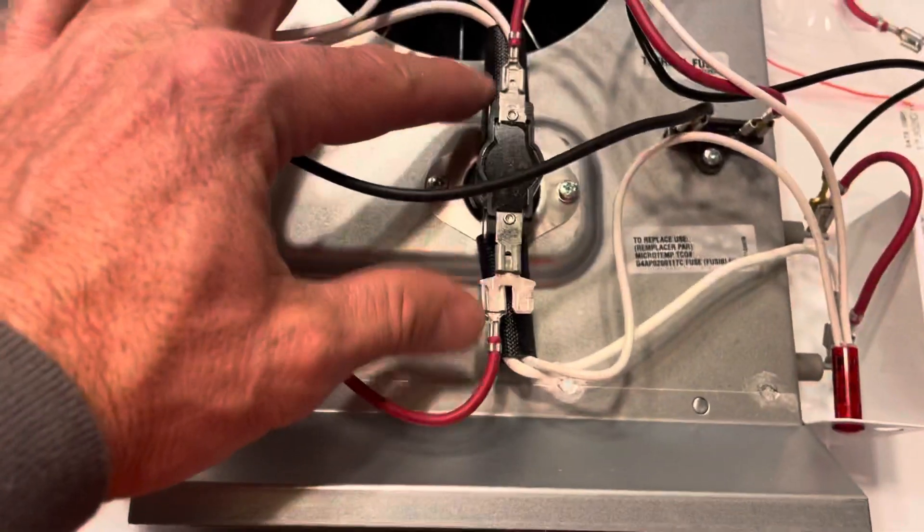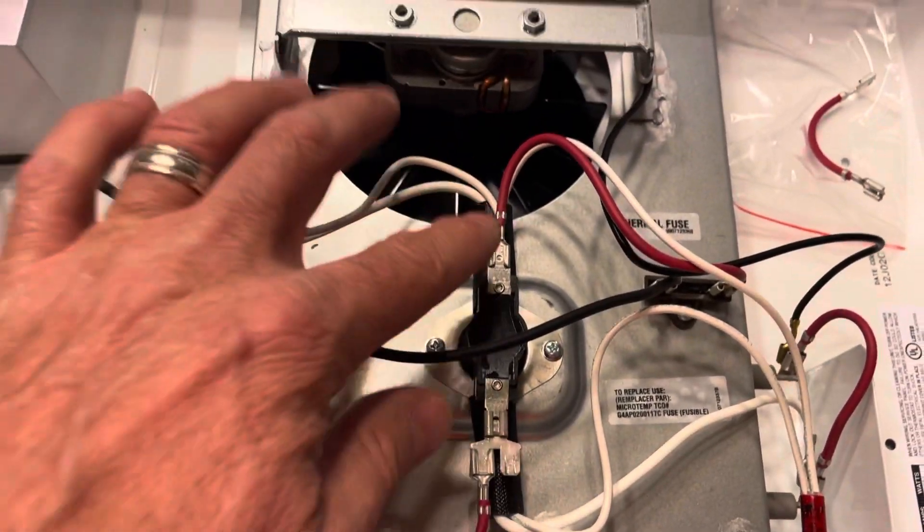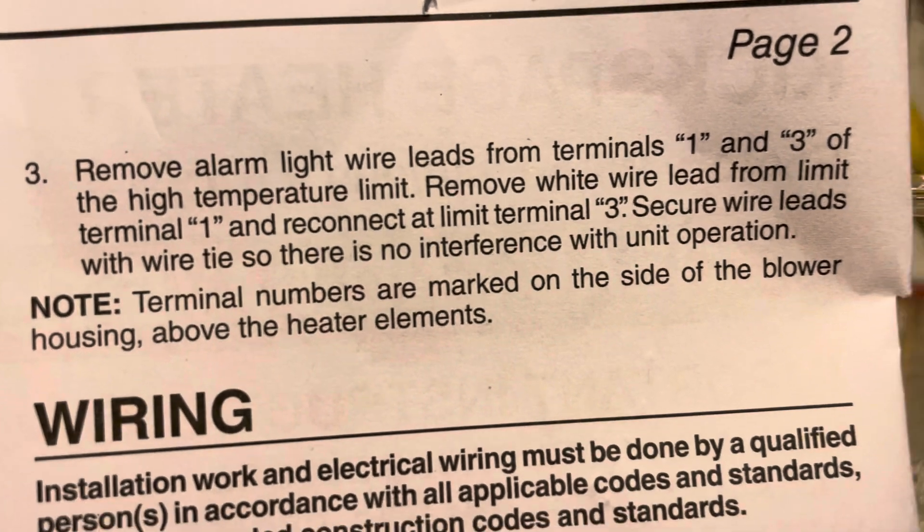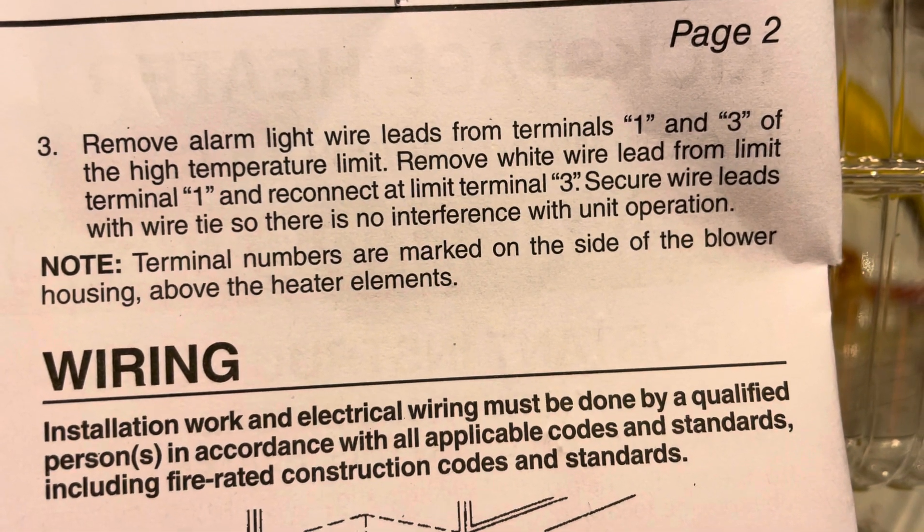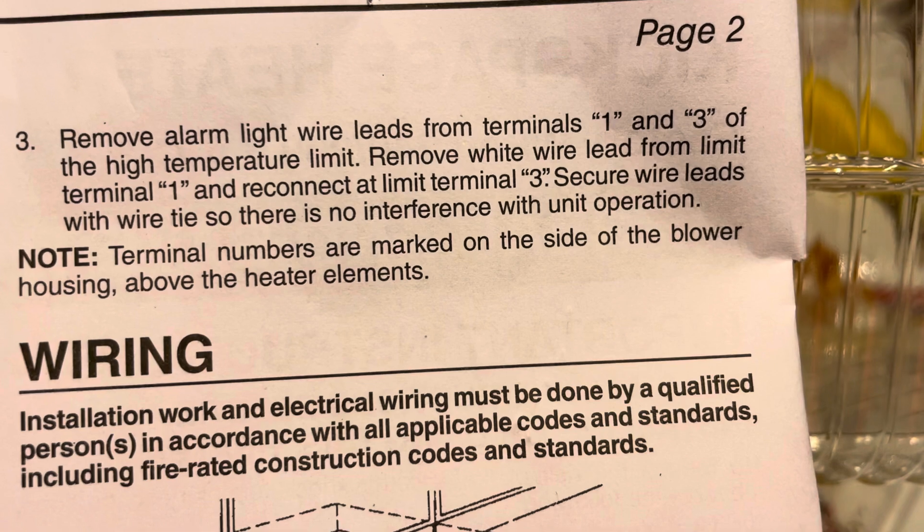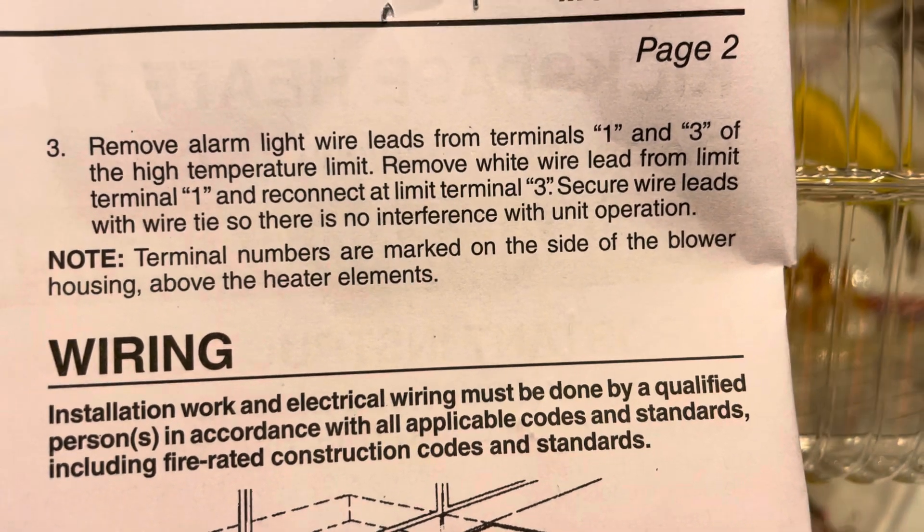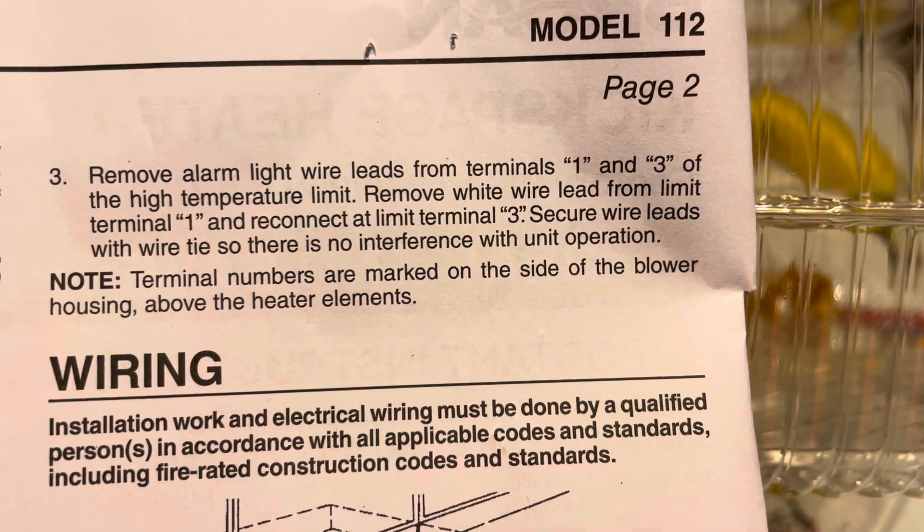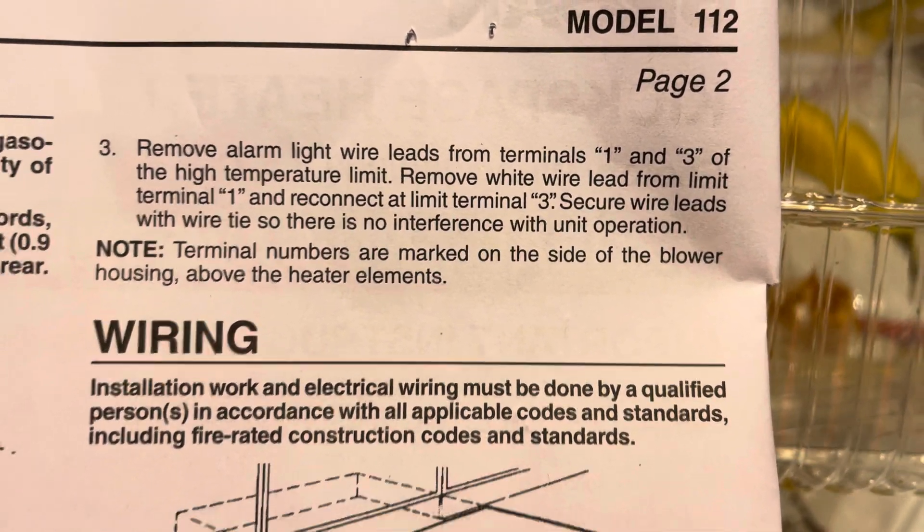I know in this case you see another wire here, but I did disconnect it. So that particular wire, that's all you're doing is you're just removing one of the lights from the equation from terminal one and terminal three. And the next step is remove the white wire lead from limit terminal one and reconnect it at limit terminal three.